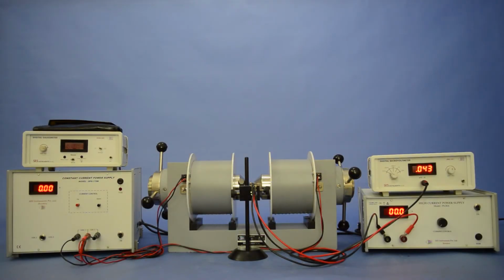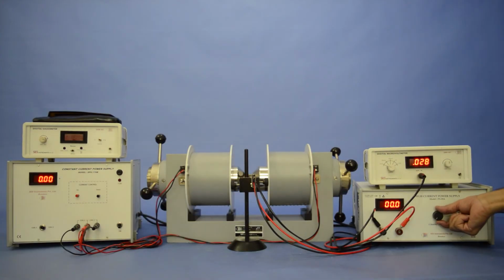Normally, we do the experiment at different probe currents 7 ampere, 13 ampere and 19 ampere. Here, I will demonstrate at 13 ampere. Keeping the probe current to 13 ampere and the magnet current 0.